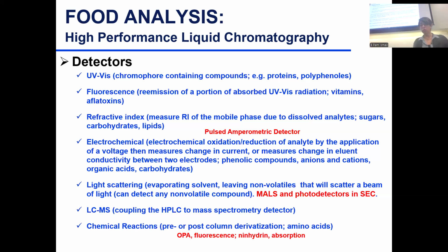Refractive index, I'm sure you're familiar with the refractive index, is very specific to the concentration and the composition of the sample. You start by measuring the refractive index of your constant mobile phase. Then when samples start coming out, there is a change in the refractive index. That change is correlated to concentration.